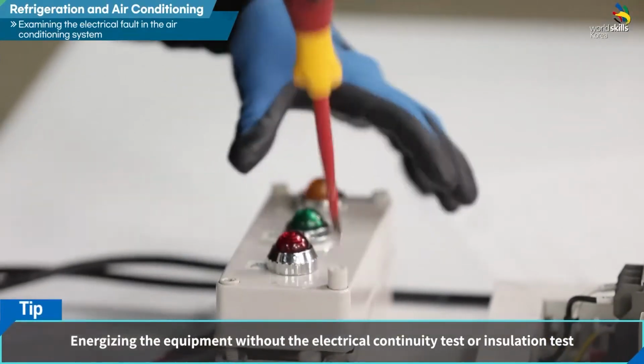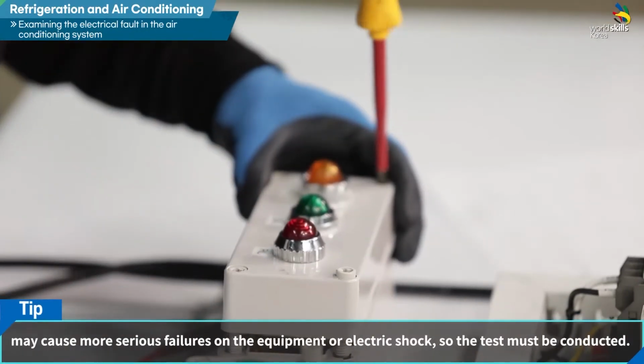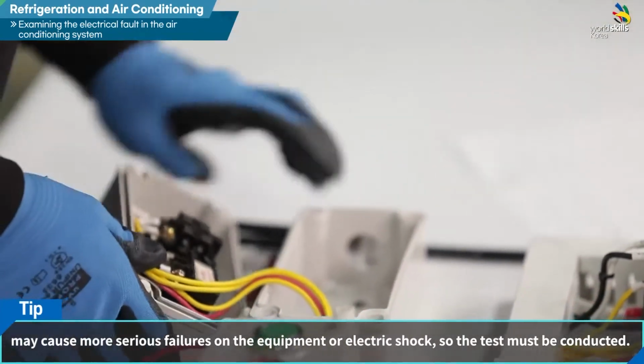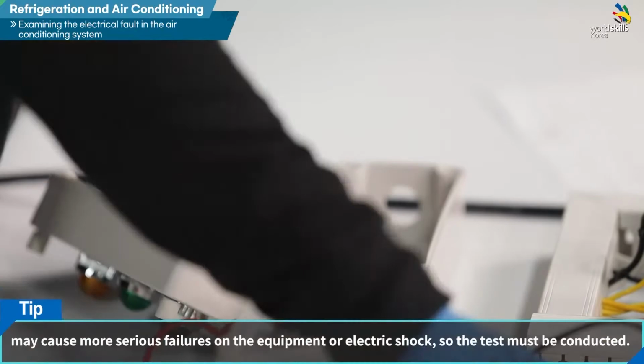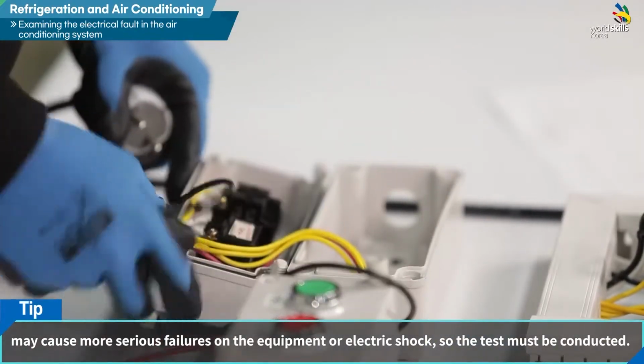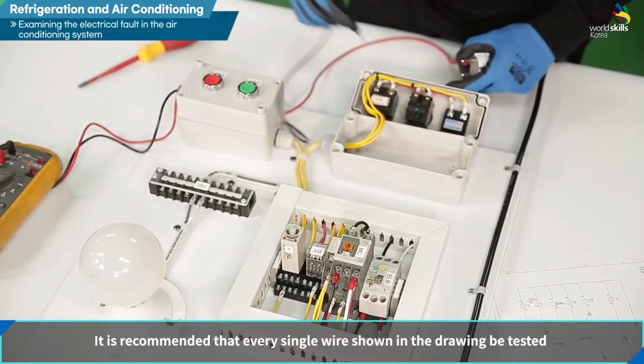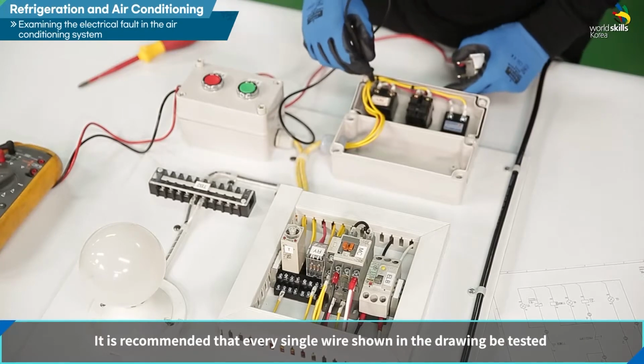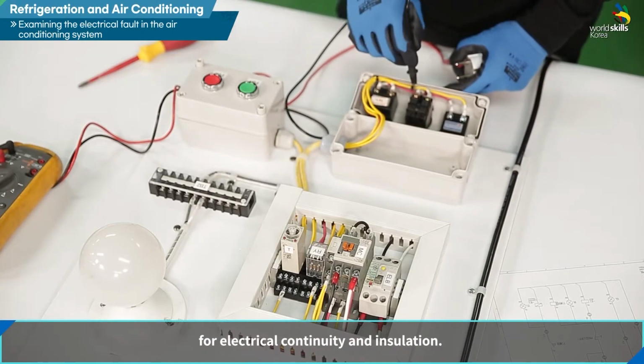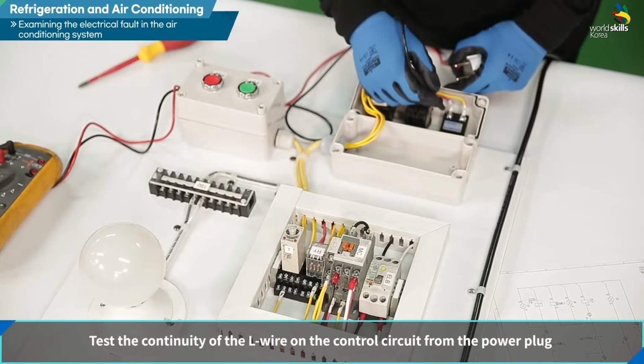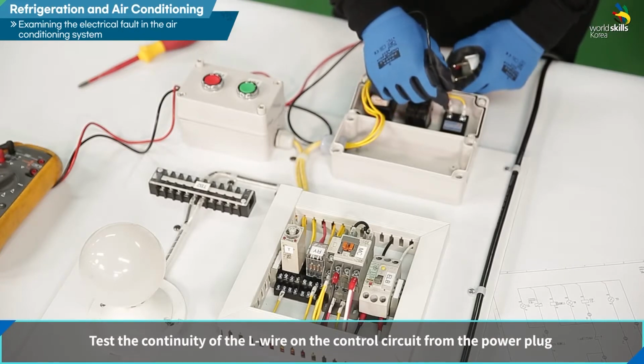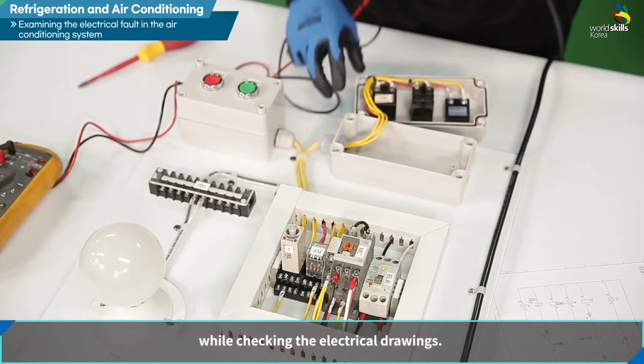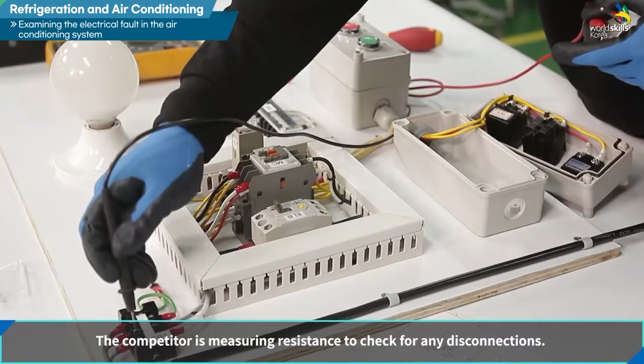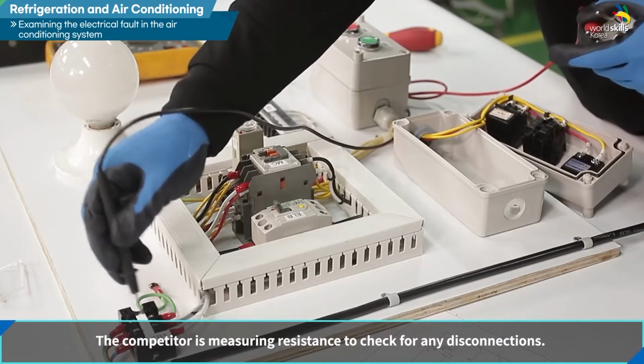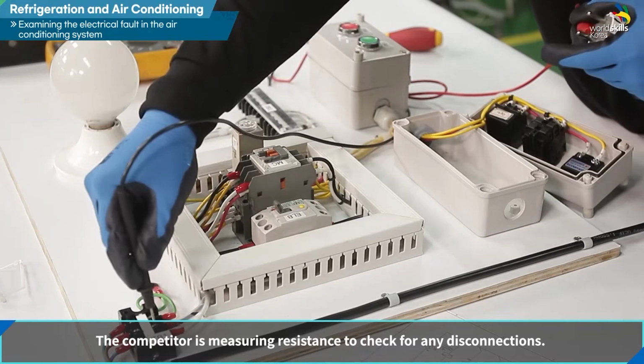Energizing the equipment without the electrical continuity test or insulation test may cause more serious failures on the equipment or electric shock, so the test must be conducted. It is recommended that every single wire shown in the drawing be tested for electrical continuity and insulation. Test the continuity of the L wire on the control circuit from the power plug while checking the electrical drawings. The competitor is measuring resistance to check for any disconnections.